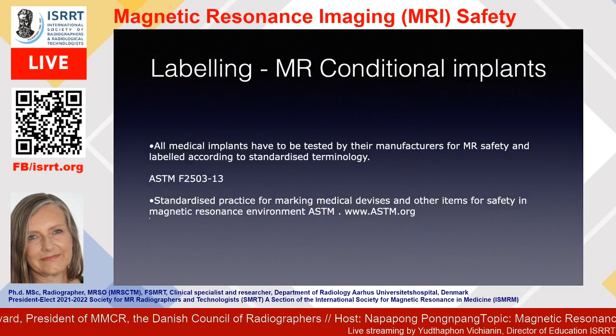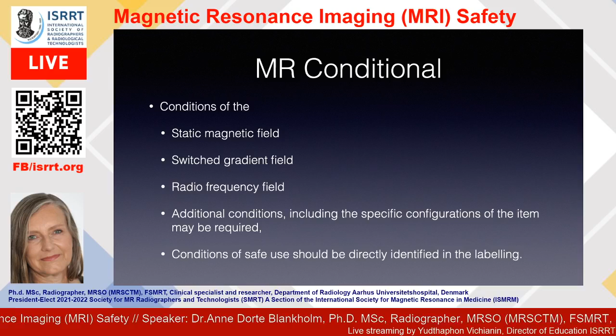So, MR conditional. It may have many conditions. It can have conditions with regards to the static magnetic field, the switched magnetic field, gradient field, and also the radio frequency field. There may also be additional conditions, including the specific configuration of the item that may be required. And the conditions of safe use should be directly identified in the labeling.